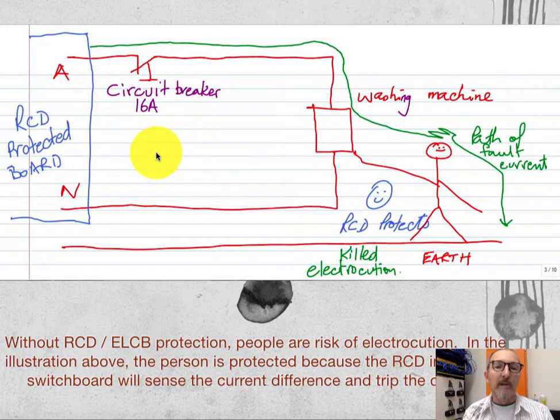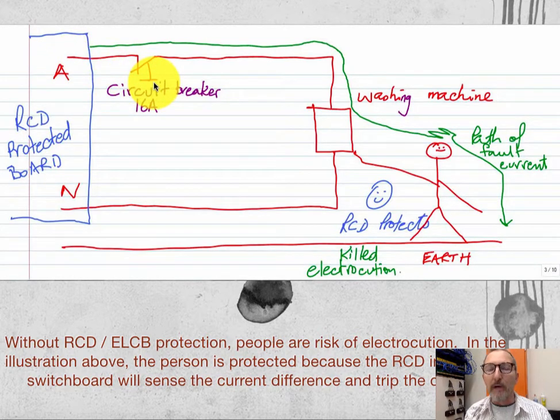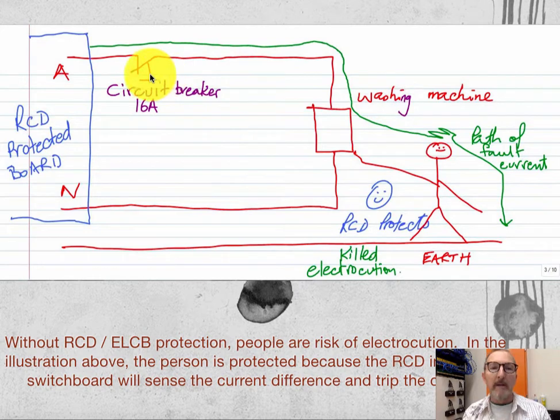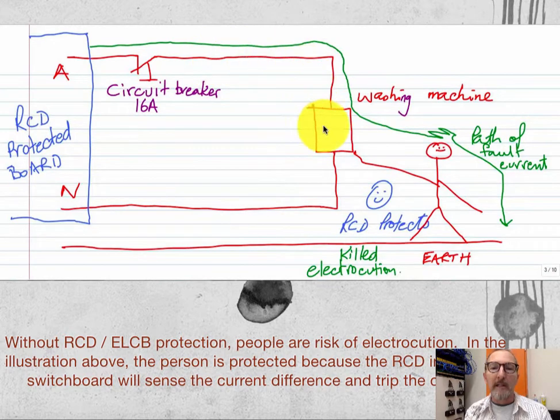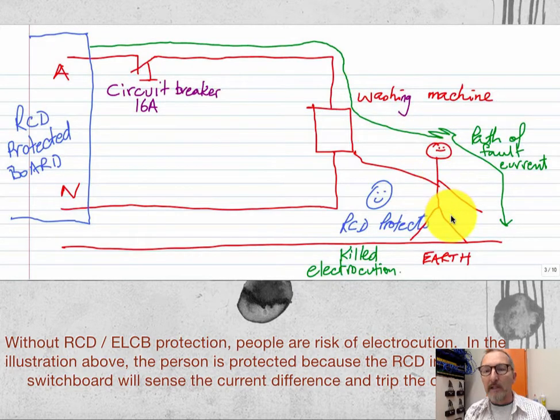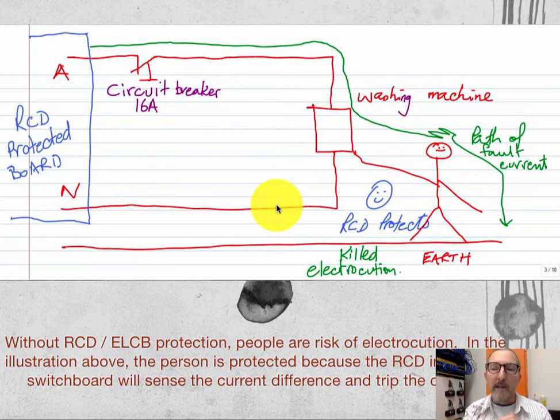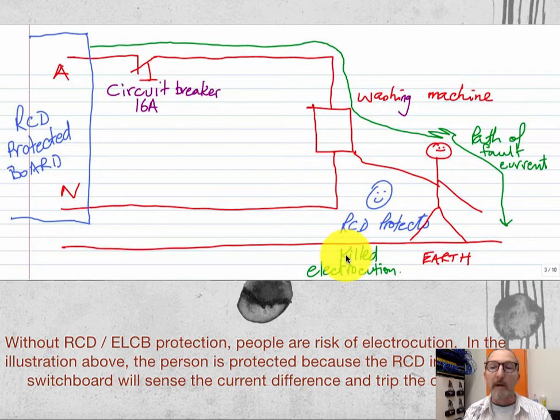Here's a real situation with an RCD-protected board with active and neutral, and following the RCD we have our circuit breaker. Remember: the circuit breaker protects property against overheated cables causing fire; the RCD protects lives. So with the RCD followed by the circuit breaker, here we've got a washing machine. Normally I've got equal current going in and coming back out. But if the washing machine develops a fault, the fault current would go down through my body to ground. As soon as we get an imbalance of 30 milliamps or more, within 30 milliseconds the RCD trips — and therefore I'm protected, otherwise I could have been killed by electrocution.